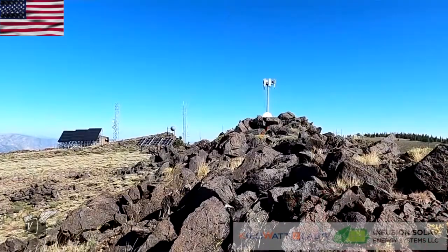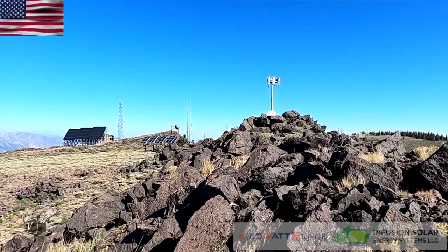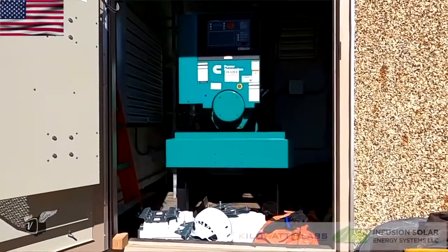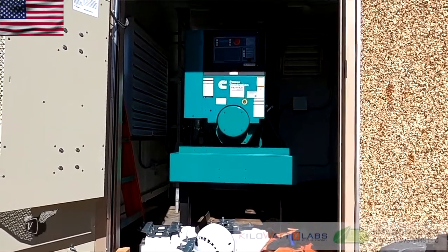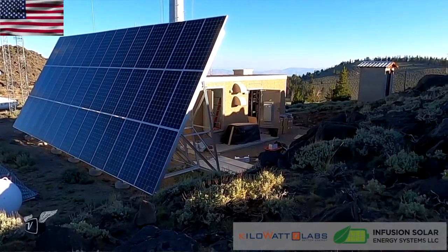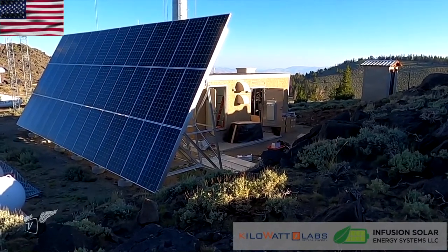The site was built 10 years ago and originally designed for a specific load. We don't have enough PV energy to power the site all the time, so we have a backup generator. In the old days of lead-acid batteries, the chemical reaction means you've got to be careful with the C-rate — the charge rate. You can only give them so much energy; if you give them too much power they get too hot, they're unhappy.